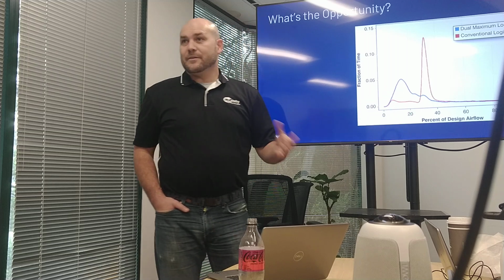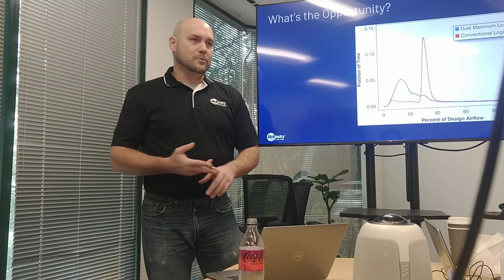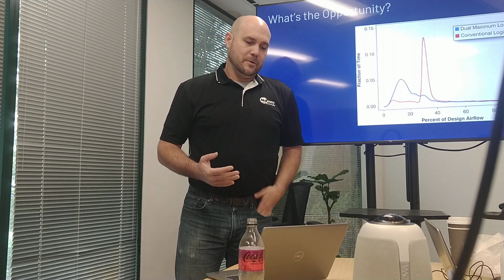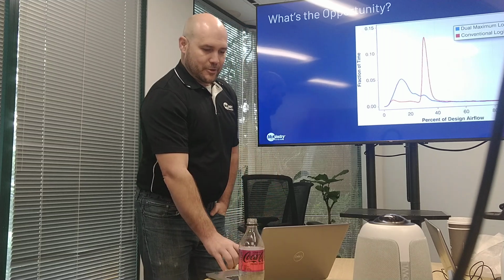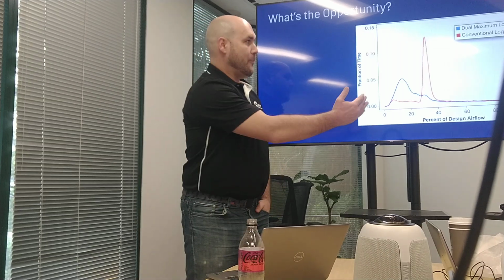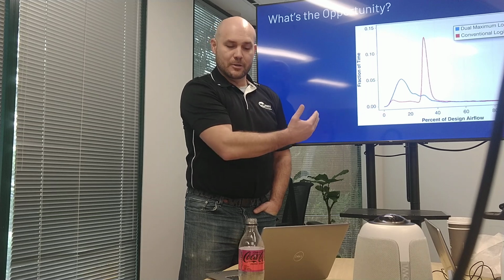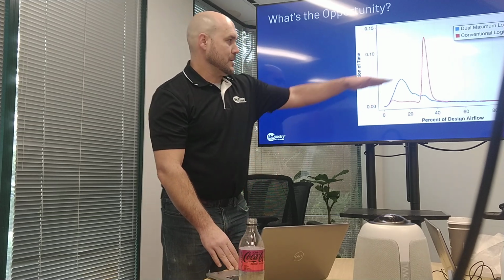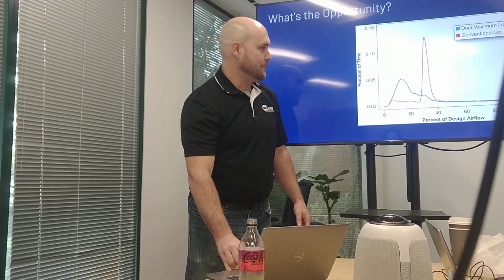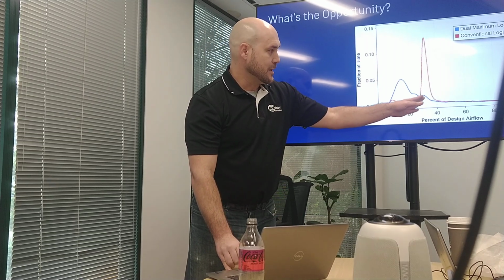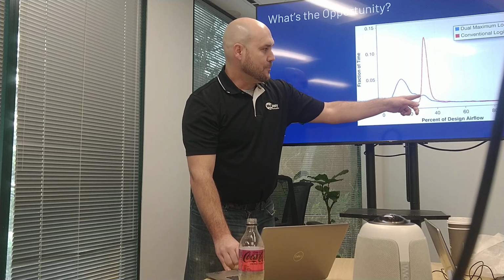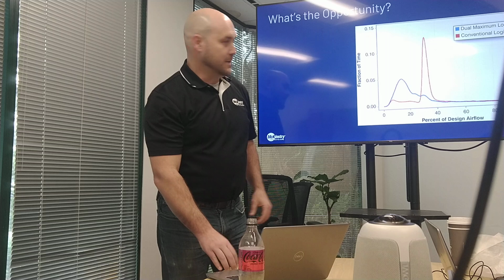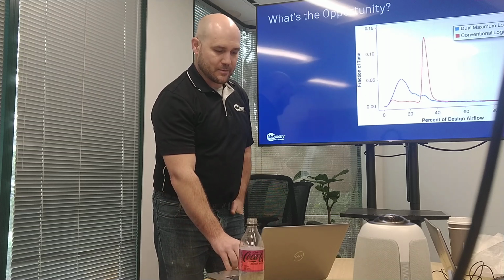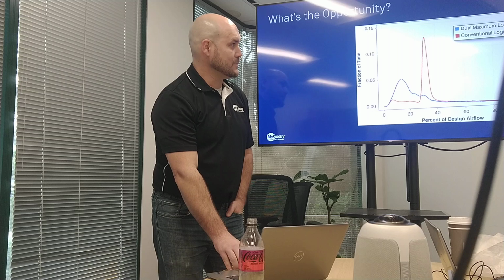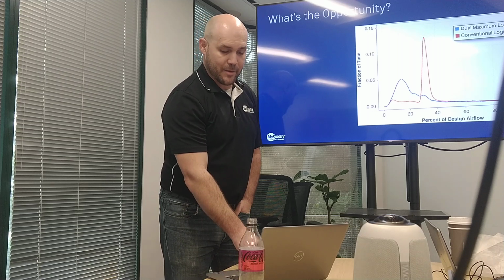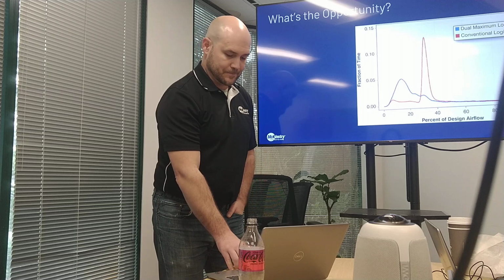There's a lot of energy savings to be had in there, not just fan energy, but cooling or heating energy as well. I think this does a really good job of capturing and illustrating how much that needle can move lower, and also sit a whole lot flatter. We'll still operate at 30%. There's a small, minor peak there, but it's a whole lot less than the very pronounced peak that we see in conventional logic, which is rampant in most of the existing buildings that we find.